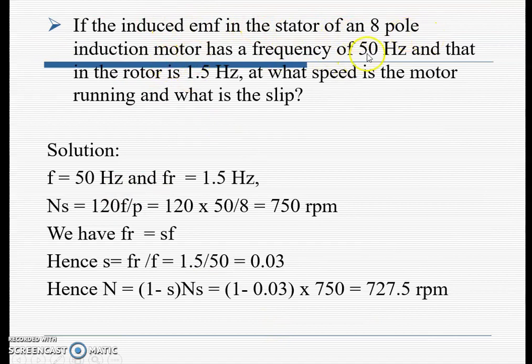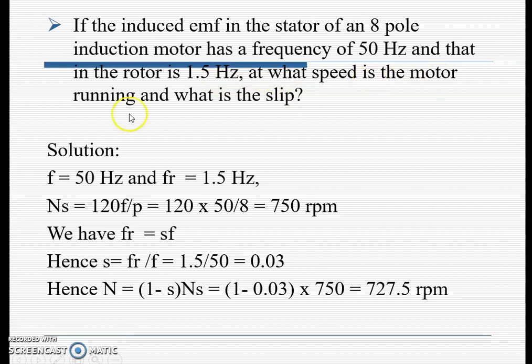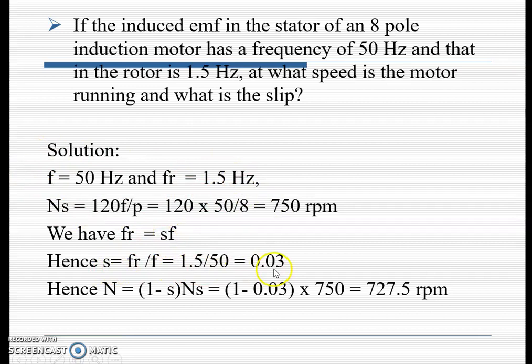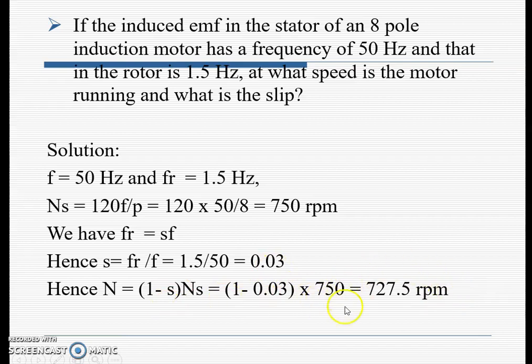Another numerical: If the induced EMF in the stator of an 8-pole induction motor has a frequency of 50 Hz and the rotor frequency is 1.5 Hz, at what speed is the motor running and what is the slip? Using f_r = s × f, slip s = 1.5 / 50 = 0.03. Synchronous speed n_s = 120 × 50 / 8 = 750 rpm. Motor speed n_m = (1 − 0.03) × 750 = 727.5 rpm.